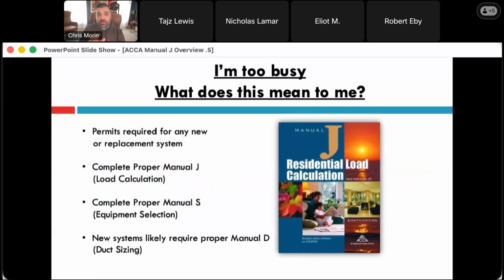So what you need to know, because everybody's busy, is because this is building code, when you pull a permit to replace a system or install a new system, you need to provide a load calculation and equipment selection across the board, right?